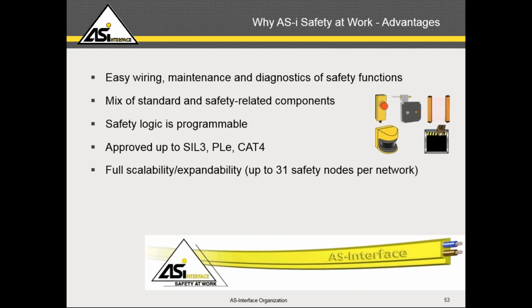So if I was to summarize what we talked about, the advantages of ASI Safety at Work, here we are showing the summary. Of course, the easy wiring, maintenance, and diagnostics. It's still just a 2-wire cable, and you simply attach devices onto the cable, either standard or safety devices on the same cable. The safety logic is simple, programmable drag and drop logic, as you have seen in the earlier slide.